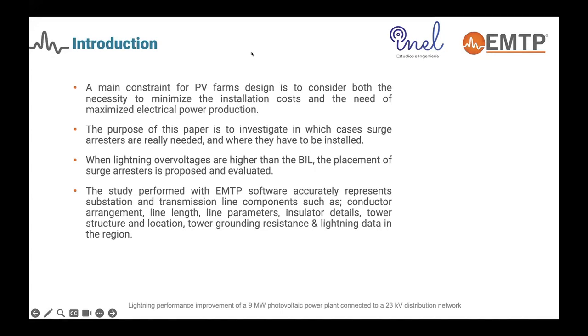The main purpose of this report, initially performed for a client in Chile, was to validate and see in which cases and where we needed to install surge arrestors, and where we needed to modify or upgrade the initial design in order to comply with the insulation level established as a design boundary. For that, we needed to elaborate an ATP model which accurately represents the main components of the power system — not the electronics of the control system, but the whole system: conductor arrangement, line lengths, line parameters, insulator details — especially to properly represent any back-flashover situation.